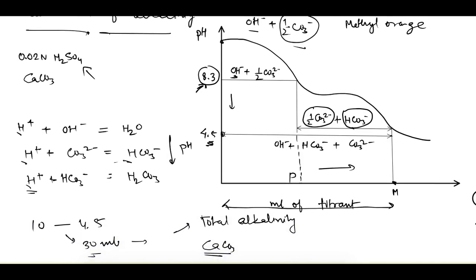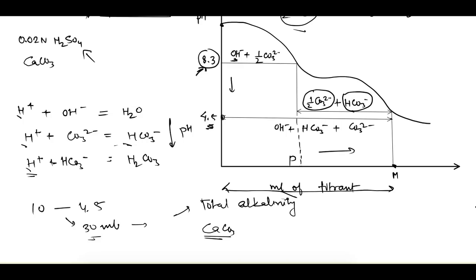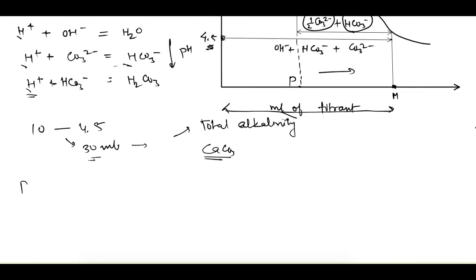Let's say the amount of titrant used up to pH 8.3 is P, and the total amount of titrant used up to pH 4.5 is M. If P equals M, that means all the titrant was consumed before the 4.5 endpoint, indicating the alkalinity was due only to hydroxide ions — we call this caustic alkalinity.